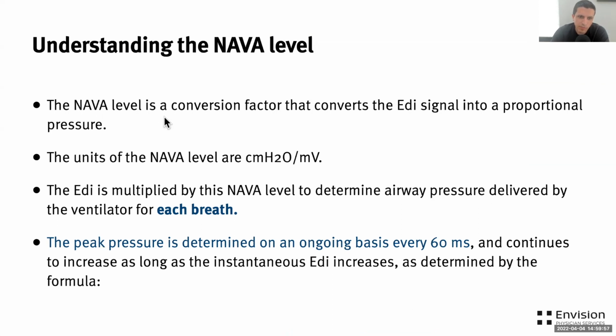The NAVA level is actually a factor. And it's a factor that converts the EDI signal into a PIP. The units for the NAVA level are centimeters of water per microvolt. And the EDI is multiplied by this NAVA level to determine the PIP for each breath. So this is something that's very important to understand: you set the NAVA level, which is a factor, and this will basically change the PIP almost breath to breath based on the baby's activity.